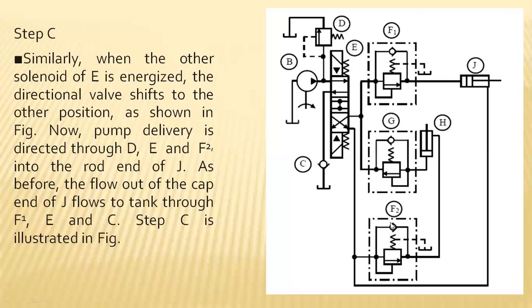So here the obstacle will be existing for the flow, because a check valve is existing here. The same fluid will be entering over this, and hence compression will be taking place within the spring. The sequence valve gets into force. So the set pressure is 5 bar of pressure, let us assume. So this 5 bar of pressure will be considered in the case of the tension existing in the spring. A 5 bar pressure limit is set. When the set pressure has been reached, the sequence valve will come into force actuation, the arrow mark will be coming into the connection, and this fluid flow will take place through the H, right?